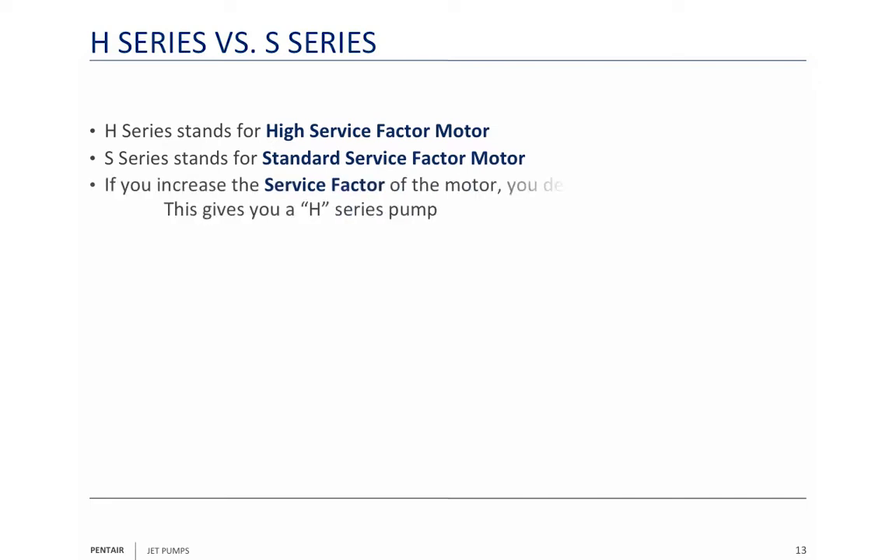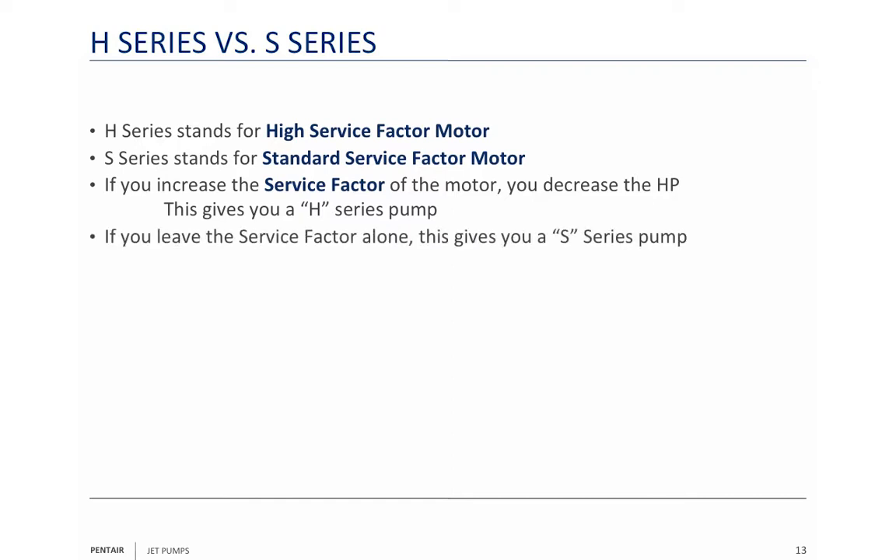The H series pump versus the S series pump: H stands for high service factor, S stands for standard service factor. What it really means is that when you use a higher service factor, you decrease the horsepower of the motor in name. The S series three-quarter horse is going to be the same pump as the H series half horse. We're going to show you that in just a minute.